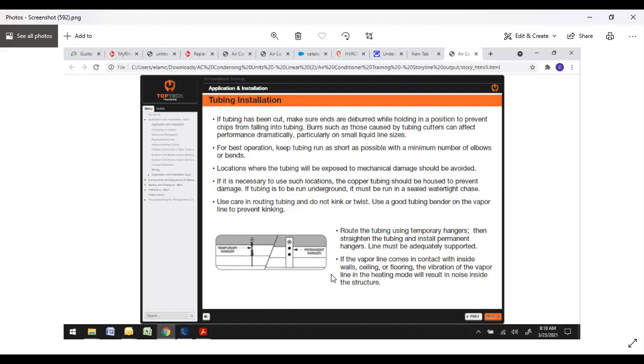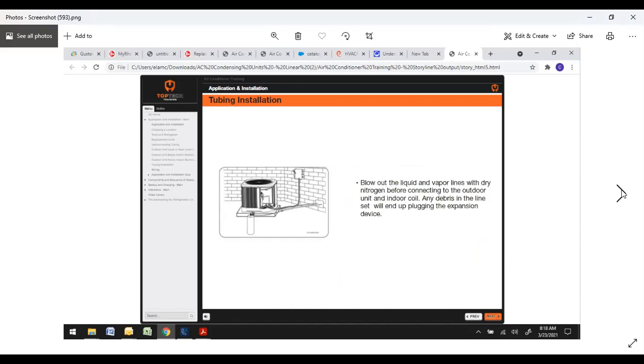If you do have to use hangers, route the tubing using temporary hangers, then straighten the tubing and install permanent hangers. Make sure they're supported so they don't get vibration, because that will cause noise complaints, especially in heat mode. It will vibrate and sometimes sounds pretty violent. Blow out any liquid and vapor lines with dry nitrogen before connecting to the outdoor unit coil. Any debris in the line set, it will end up plugging the expansion device. I can almost guarantee you that.